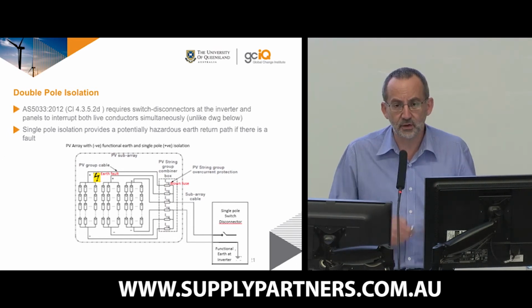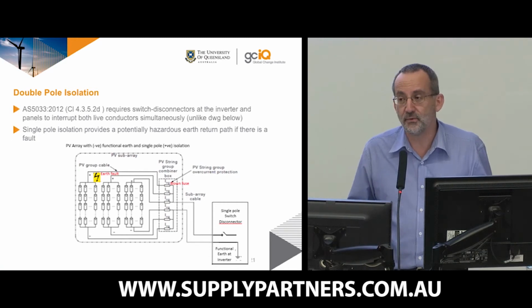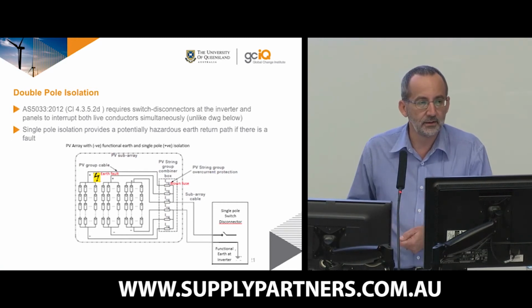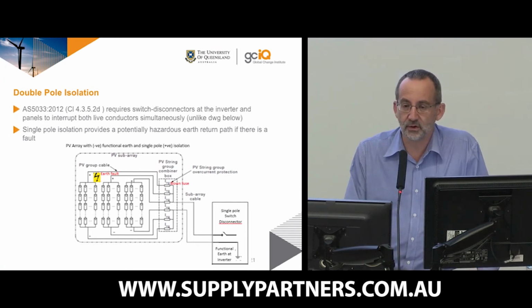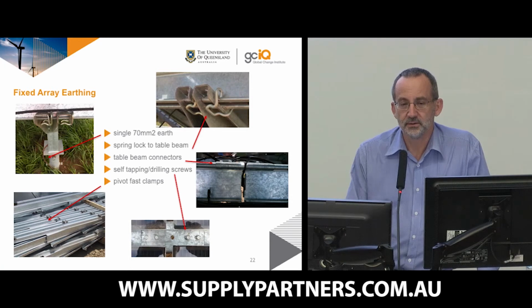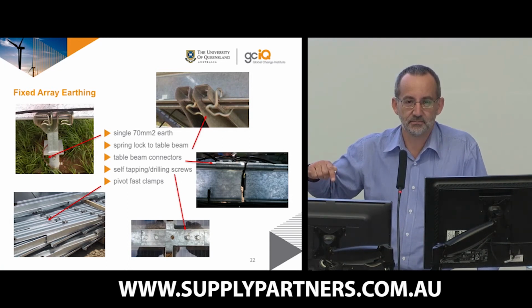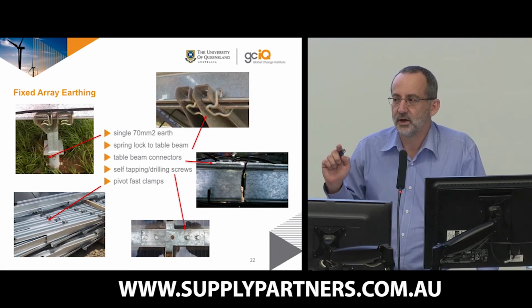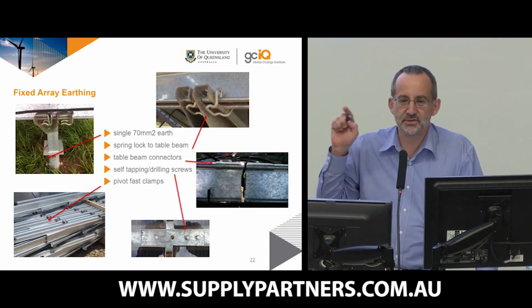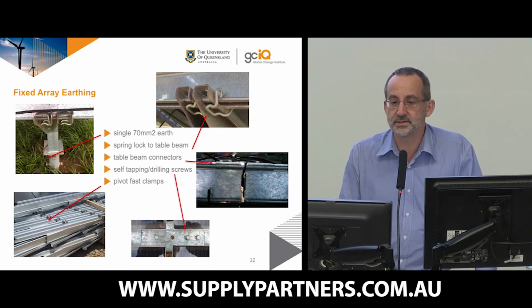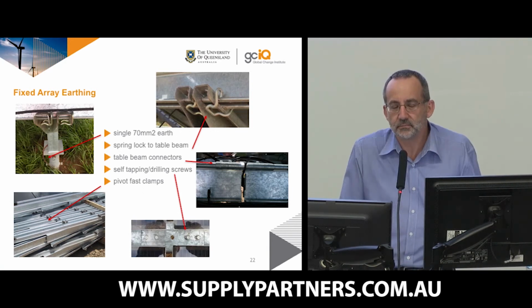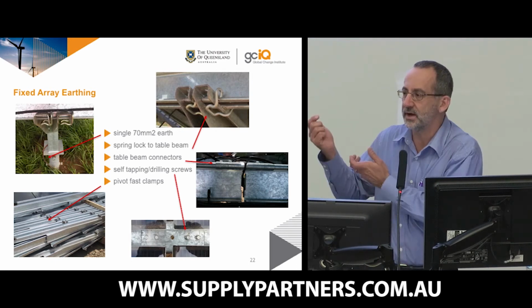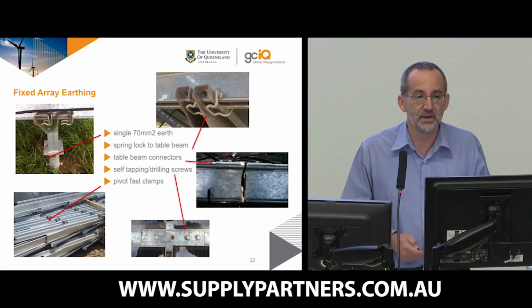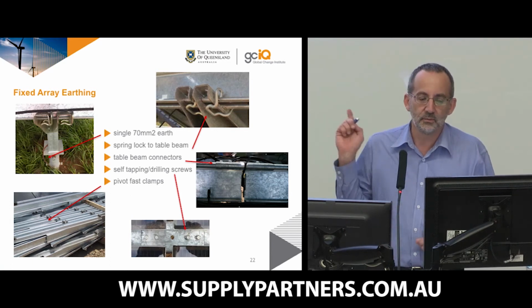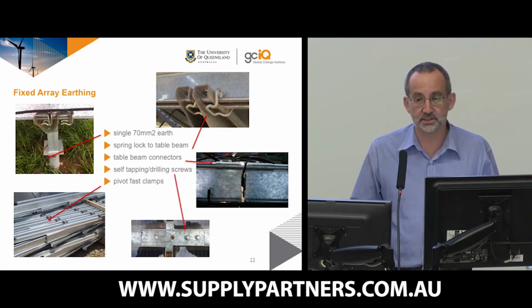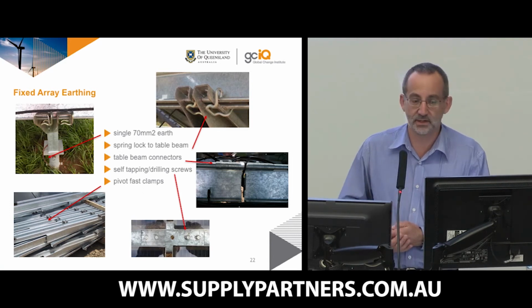One of the other interesting things, when you have a large number of strings in parallel, and we've got 480 strings in parallel on each inverter, is that if you do have a fault to ground, the fuse will blow, but from backfeed from the other strings. And once that fuse is blown, your single string that's faulted continues to feed into a fault. It's not cleared, it stays there. And it's something that people don't expect. Most of us who have gone through the ranks of working with AC circuits and so forth, if there's a fault, you expect it to be cleared. With these systems, they're not cleared, and it will stay there at least until the following day when the inverter checks the insulation.